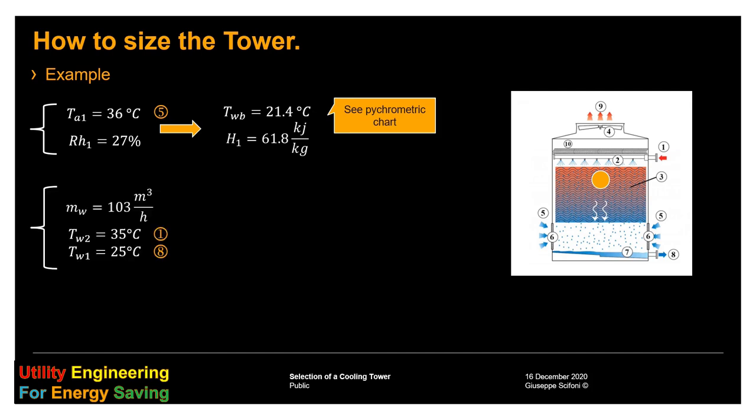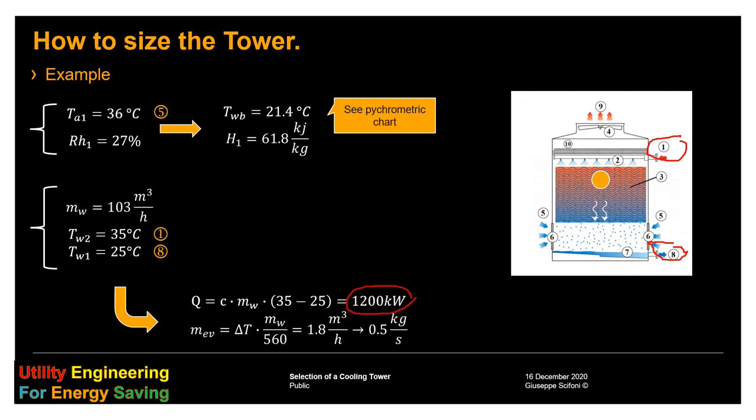From the process side, we know the flow, 103 cubic meter per hour, the entry and the leaving temperature, which corresponds to the position one and eight in the picture. Therefore, we can determine the heat transfer, 1200 kilowatt, and the mass of the water which evaporates, 0.5 kilogram per second.